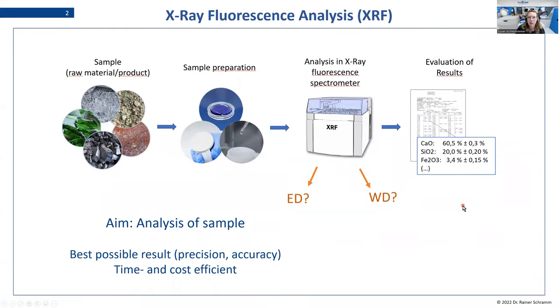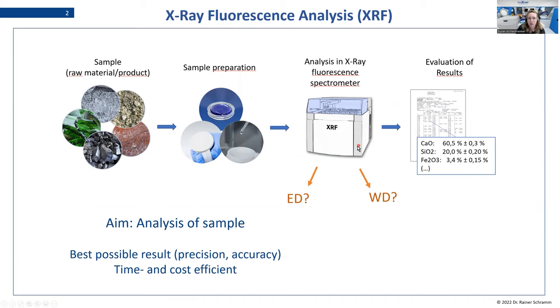First of all, we are dealing with X-ray fluorescence analysis, no matter which method we are using. We are having some kind of a sample, doing some kind of sample preparation — whether we are making a pressed pellet, fusing a fused bead, or having some liquid or powder directly put into a cup for measurement. In the end, the sample will be measured in an X-ray fluorescence spectrometer and we will get results in the form of element or oxide concentrations. There are two options: the ED system or the WD system.